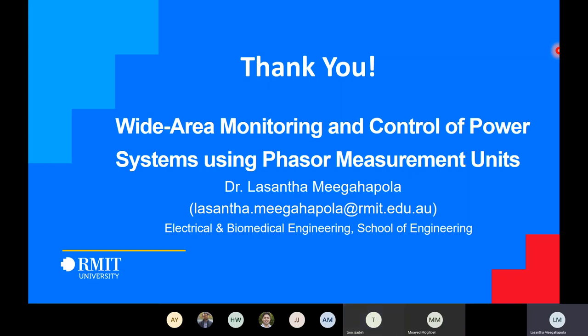It's slow because you have to get rid of a lot of harmonic components. Whatever PMU the manufacturers develop, it should conform to the standard, and the standard specifies a range of tests, even with the 50th harmonic. When they first drafted the IEEE C37.118 standard, they put a lot of rigorous testing measures into it. Later, in 2014, they amended the standard to allow some relaxation, because manufacturers complained they couldn't come to such a great accuracy. So I think that is the main hurdle at this point.